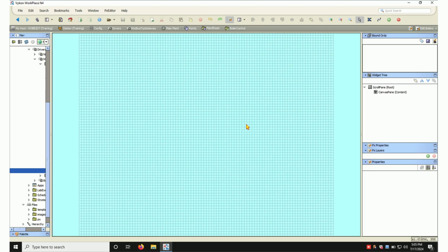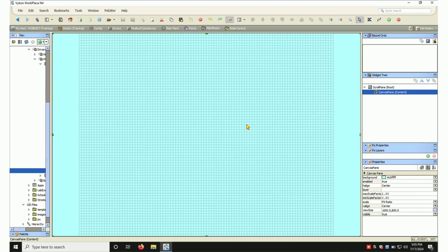1080 pixels tall. Now, Niagara graphics these days are pretty comprehensive in that they support this function called scalability. And that means that if you view the graphics on one laptop with a small screen, the graphics will fit. And then if you come on with a different type of display, that's maybe like a 4K monitor, the graphics will dynamically resize to fit the target screen that's being used. But there are still some very careful considerations you have to make about how you set that up.